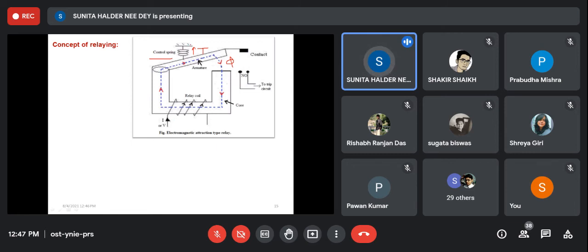That is called the restraining torque or restraining action. It is helping the relay to stay in the open condition, and there must be a torque developed that will help to move the relay to the closed condition. That is called the operating torque, T suffix O, and this may be T suffix R, right? And what is happening when there is a movement in the moving portion? Then it is closing the contact, NO contact to NC, by this strip of conducting material, and that will close the trip circuit, which will energize the circuit breaker trip coil circuit. So this is the concept of relaying.